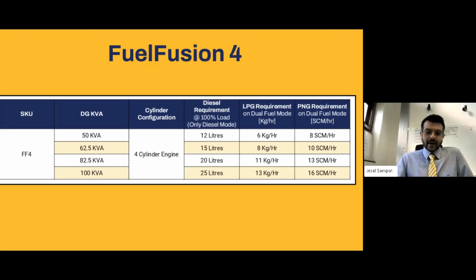If you want to switch from 100% diesel mode onto dual fuel mode, you will need 6 kgs of LPG and the balance 6 liters will remain diesel. So you will replace 6 liters of diesel with 6 kgs of LPG, and that is where the cost saving comes into the picture. Similarly with PNG, you will replace 12 liters of diesel with 8 SCM per hour of natural gas, and the balance 4 liters will remain on diesel mode. So if it is natural gas, you will need 8 SCM natural gas and 4 liters of diesel. That is where the cost saving part comes. Of course, the bigger the generator, the more the cost saving. So the FF4, FuelFusion 4 for 50 kVA up to 100 kVA.